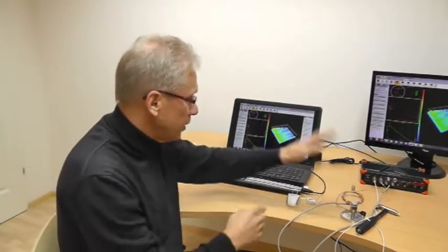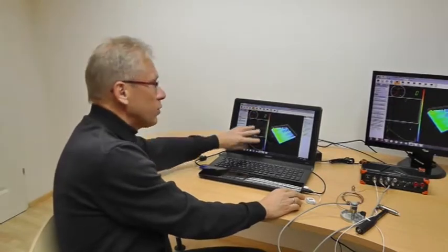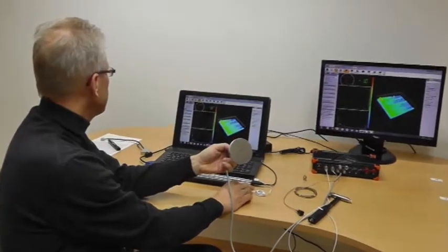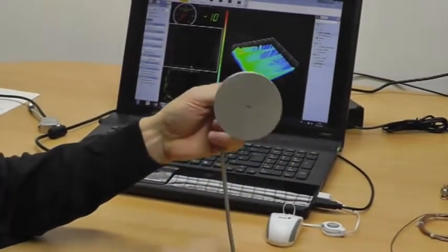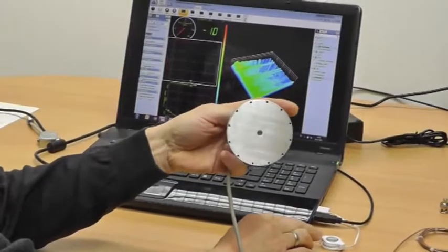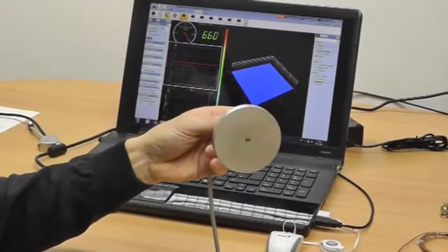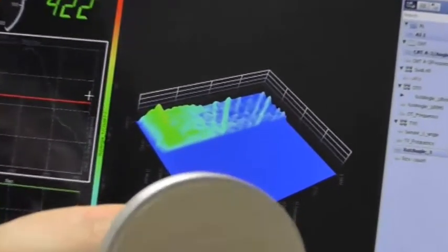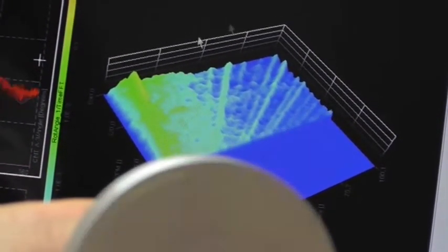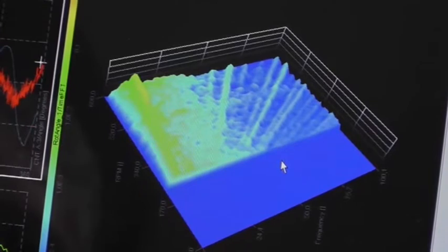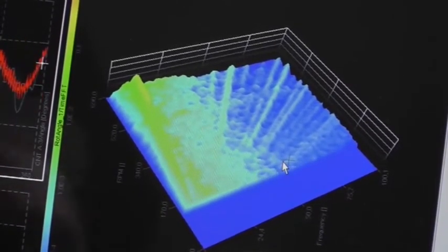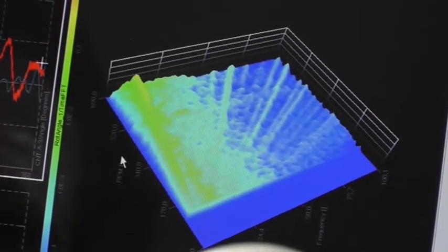This could be one part, but now I explain only this left part of the window. How about the right part? I just stop and start again and make this run again. Now I make a coast down from 500-600 RPM to zero. Here I can show you which RPMs are critical RPMs. It's shown using the auto-tracking window. And this auto-tracking and the whole setup also is very easy to do and very convenient.